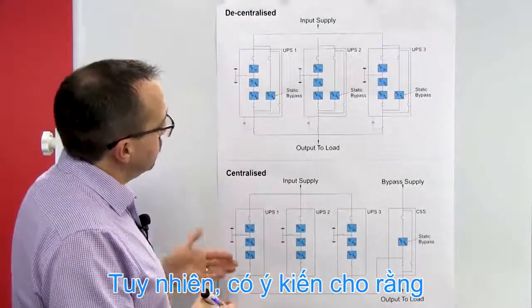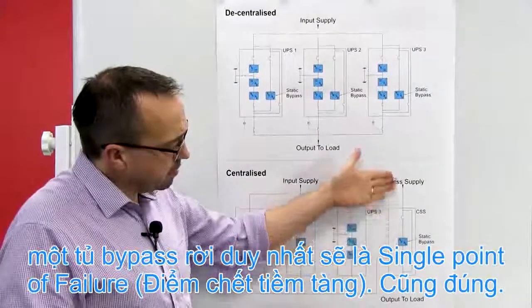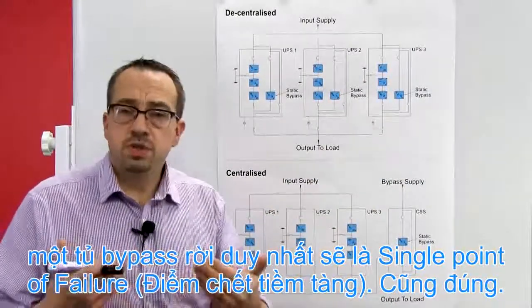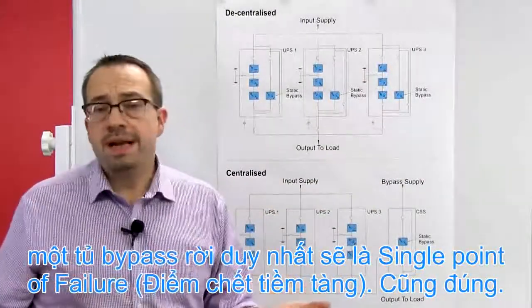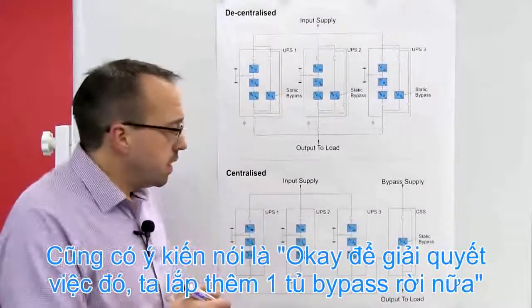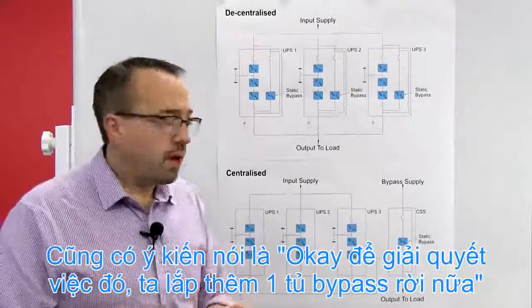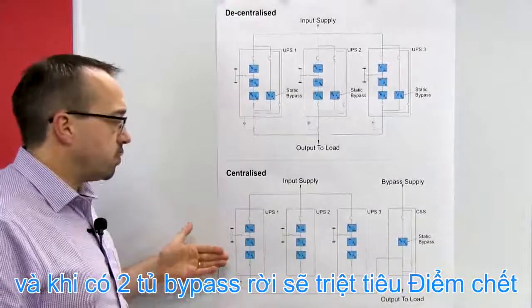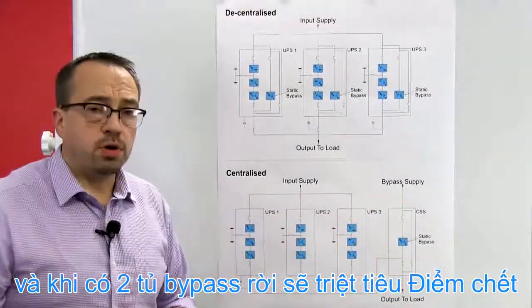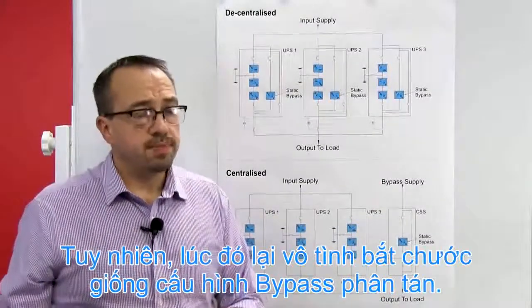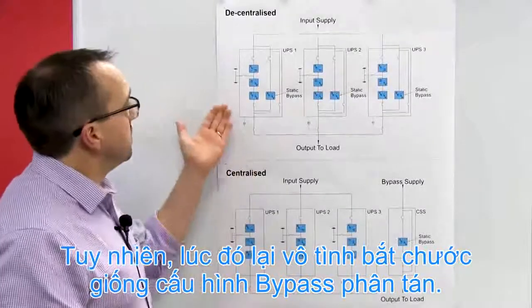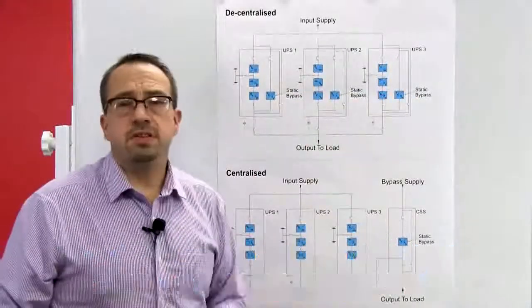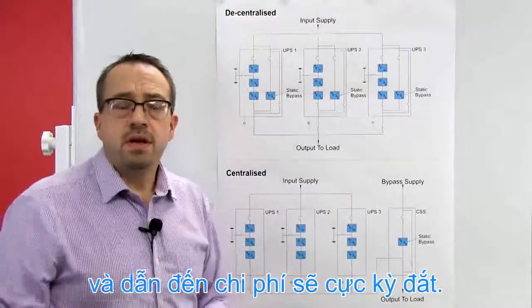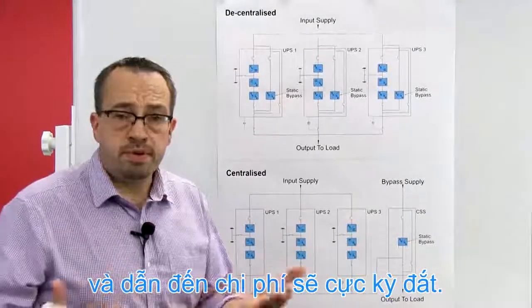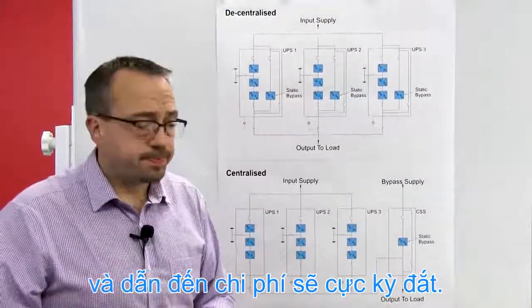However, some people do consider having the single bypass module to be a potential single point of failure, which quite rightly it is. Now, some people will say, well, okay, in order to get over that, I can just add in a second bypass module and hence have 2 bypass modules to remove that single point of failure. However, by doing so, you are simply mimicking the decentralized approach. So it would be a very, very cost prohibitive method of installation.